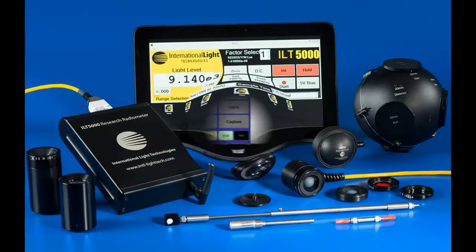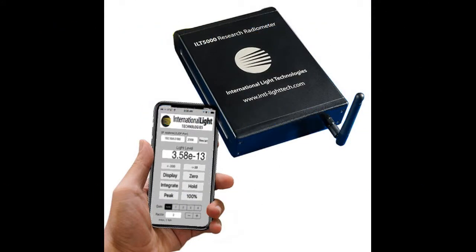This full range is also applied to the light level readings when paired with a calibrated ILT sensor. The device has built-in wireless technology, 4 to 20 milliamp output, and an SMA connector for measuring non-ILT sensors.